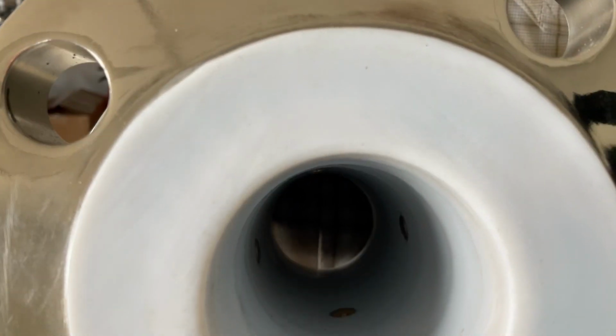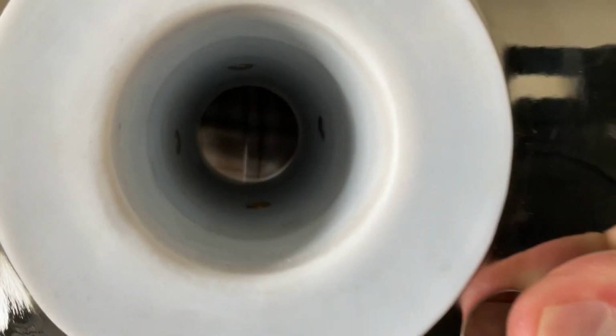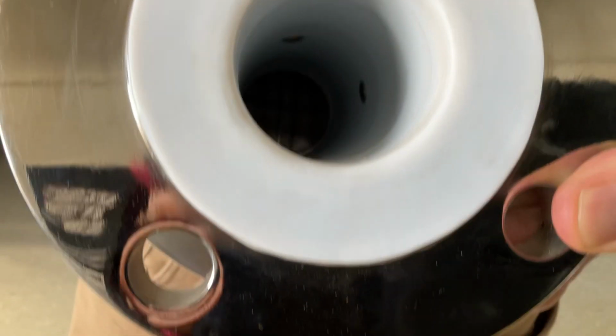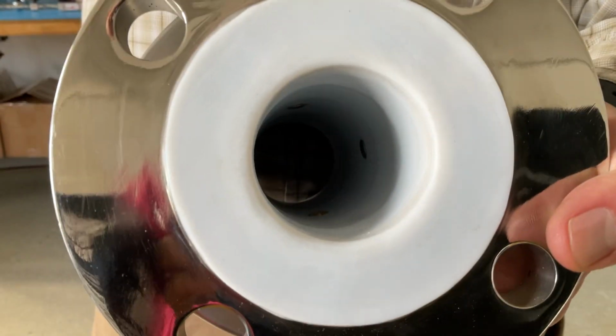Now, I see 4 things in there, but there's 3 electrodes? Yeah, 3 electrodes. What's the 4th hole? Let's take a look. Oh, yeah, this one has 4. So some have 3 electrodes, some have 4 electrodes. Perfect. And this plastic is the liner. This is Teflon, but for cement applications, we use polyurethane because it's more durable. And for the electrodes, standard is 316L stainless steel, and we could upgrade it to tantalum, titanium, or tungsten carbide. But it seems like the standard steel will work just fine for most. That's correct.